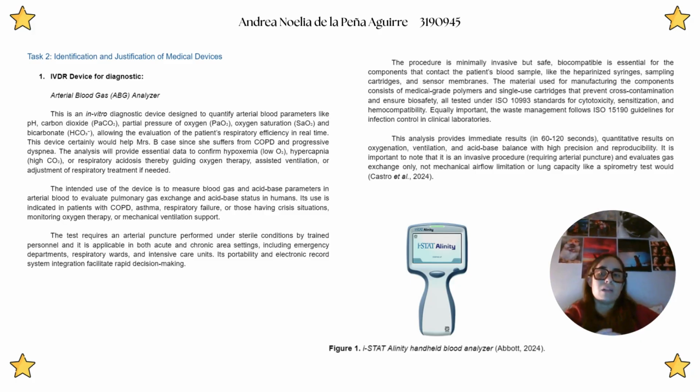Its materials include medical-grade polymers and single-use cartridges, all tested under ISO 10993 standards for cytotoxicity, sensitization, and hemocompatibility, while following ISO 15190 for infection control. The main advantage is that it provides immediate quantitative results within 1 or 2 minutes. However, it is invasive since it requires arterial puncture.